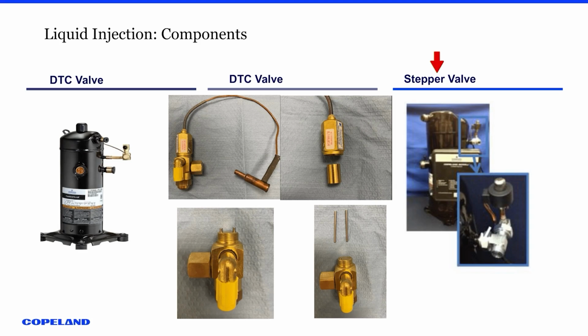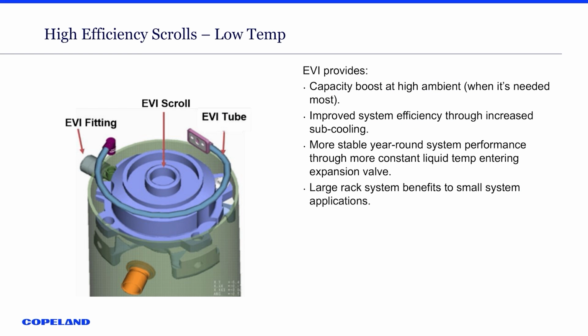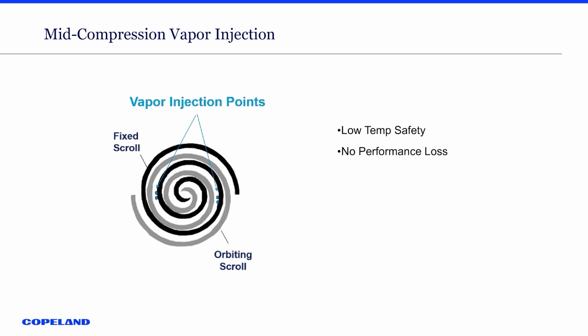The larger compressors, instead of using a manual valve like that, use an electronic valve. Okay, so we've got a little stepper valve over there. This is showing another way. This happens to be a vapor injection, but this little spot right here goes into that tube, and then it brings that tube into our scroll set to cool it down. And this just shows the little ports inside that scroll set to cool down that compressor, okay?